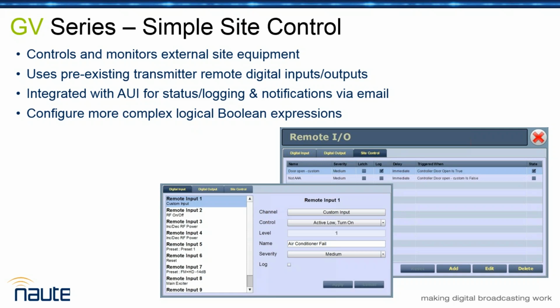Beyond that, I've got a guy who uses the tower light. He measures the current through the tower lighting, converts that to a voltage, runs it through a comparator, and uses the high-low to trigger a tower light alarm. So if the current falls below what it would take for all the lights to be working perfectly, even if just one is off, it falls below the comparator trip point and sends out an AUI message, email or SMS, or an alarm in the log that they may have a problem.